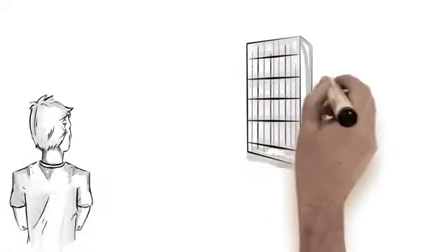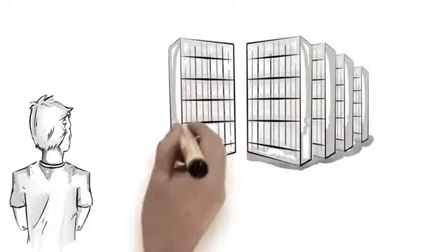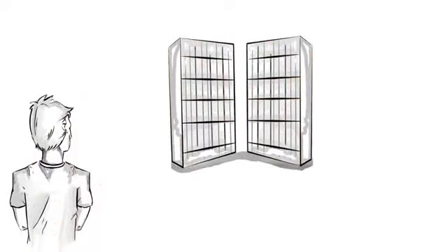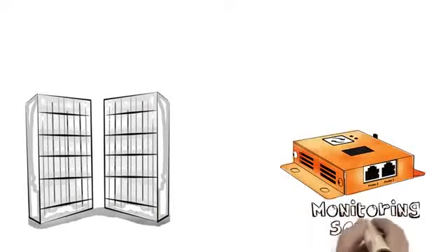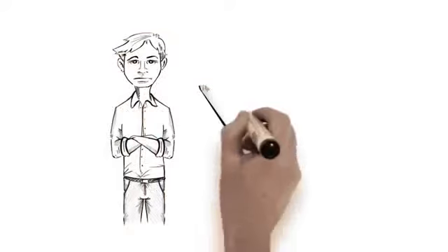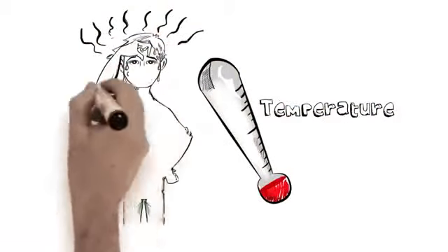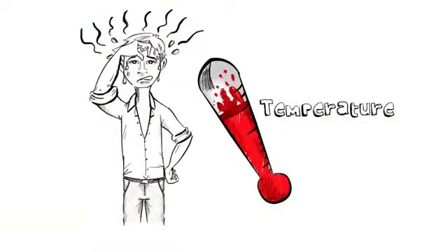Implement those with the Servers Check sensors. It applies not only to data centers, but also to smaller server rooms with just a few racks. Let's talk about ambient monitoring first. Ambient monitoring is monitoring at a room level. This level of monitoring will alert you when air conditioning units start failing. Temperature should be between 18 to 27 degrees Celsius or 64 to 81 degrees Fahrenheit.